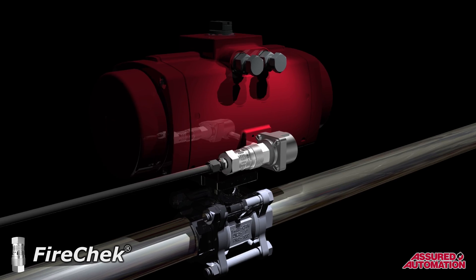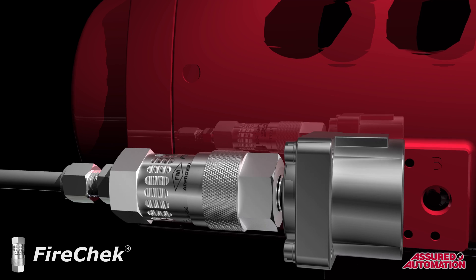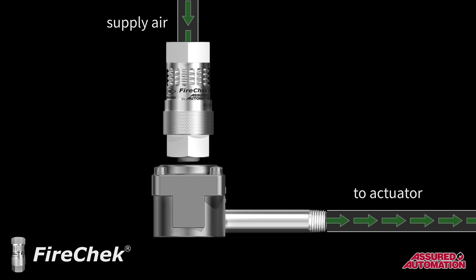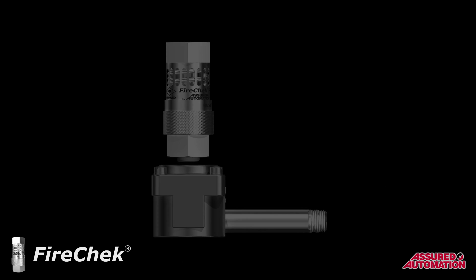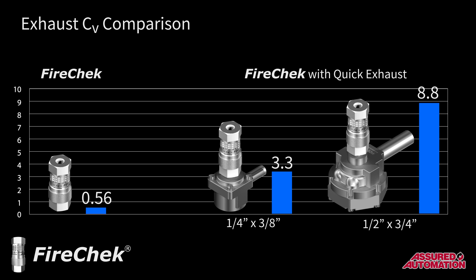Installation of the FireCheck with quick exhaust is similar; however, the outlet, or downstream side, has the quick exhaust diverter valve attached. These units function exactly the same as the FireCheck valve, except when they are triggered, the exhaust from the actuator is diverted through a larger exhaust port, providing a faster evacuation of air from the pneumatic actuator. The exhaust CV increases from 0.56 to 3.3 for the 1/4-inch by 3/8-inch model, and up to 8.8 for the 1/2-inch by 3/4-inch model.